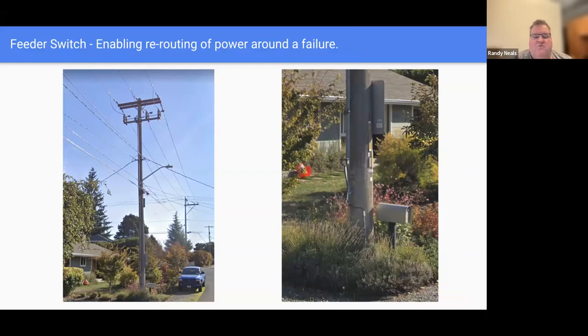Now you might wonder, why would you want that? You want the power on all the time. Well, in this particular area there's a hospital nearby my house, and they like to keep the power on there with very little interruption. Both sides of the feeders that come from Duwamish are arranged in a ring, and they can open switches around the ring as needed to isolate faults. So if a tree contacted a wire at a certain spot, they can identify the switches on either side of that point, open those switches, and that leaves just that small piece of the network unenergized because the tree is still on it. That leaves it dead, but they can restore power to the rest of the network.